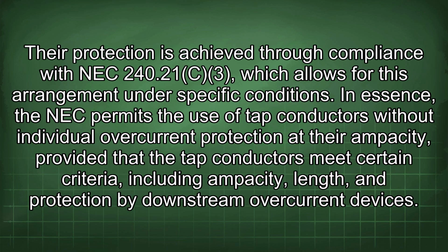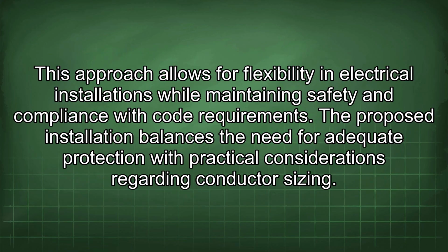Their protection is achieved through compliance with NEC 240.21(c)(3), which allows for this arrangement under specific conditions. In essence, the NEC permits the use of tap conductors without individual overcurrent protection at their ampacity, provided that the tap conductors meet certain criteria, including ampacity, length, and protection by downstream overcurrent devices. This approach allows for flexibility in electrical installations while maintaining safety and compliance with code requirements.